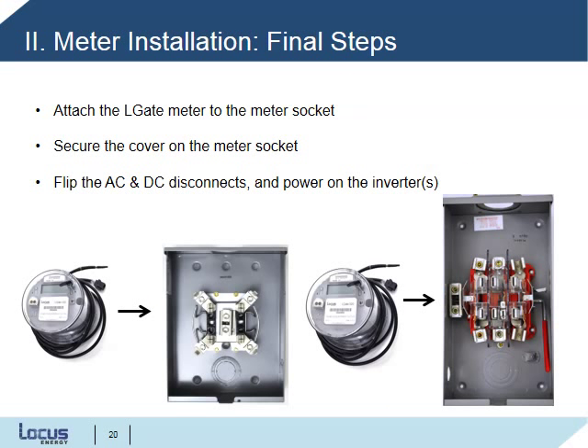Final steps in the meter installation. First is to attach the LGate meter to the meter socket by carefully sliding the meter tabs into the jaws. Secure the cover on the meter socket. We recommend using zip ties to secure any unused RS-485 and Ethernet cable inside the meter socket. Finally, flip the AC and DC disconnects and power on the inverters.